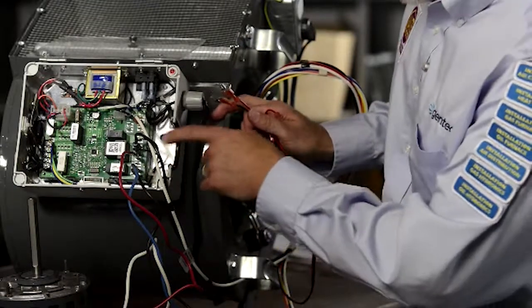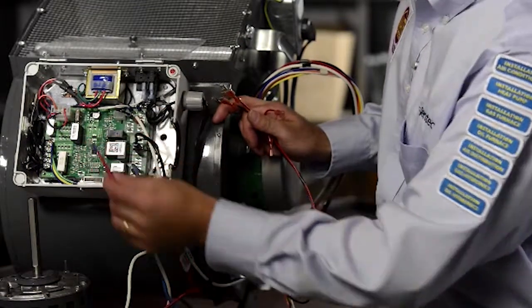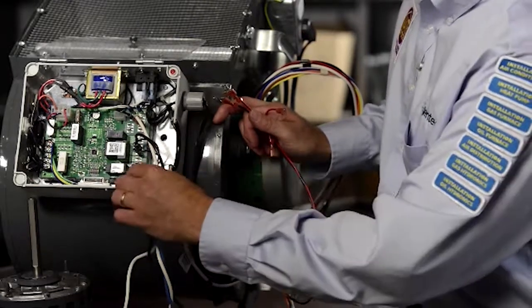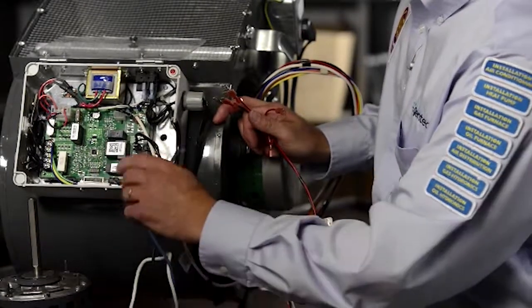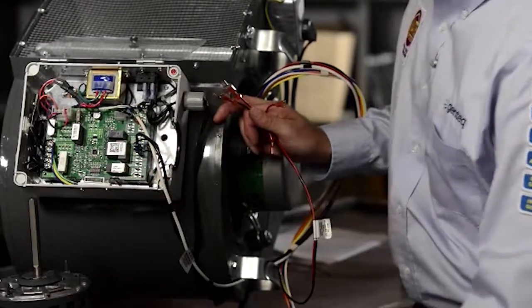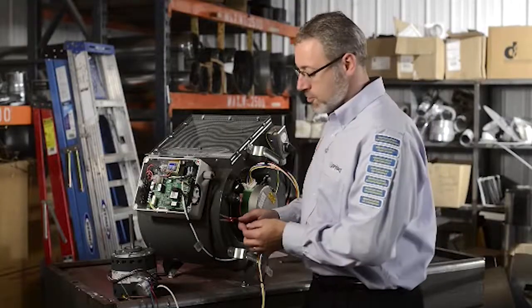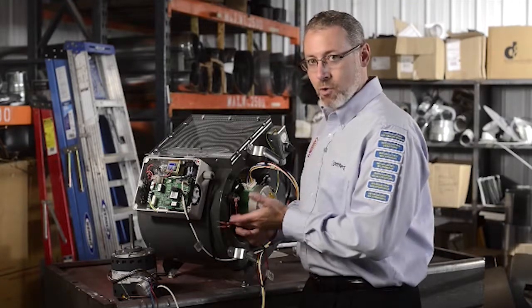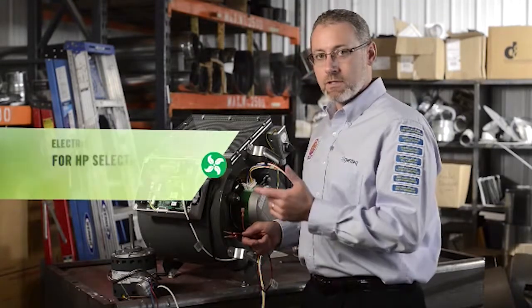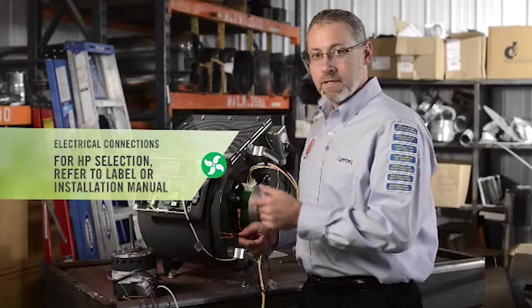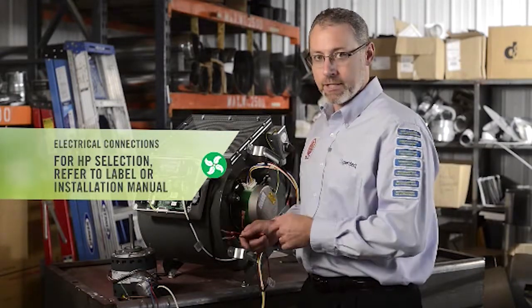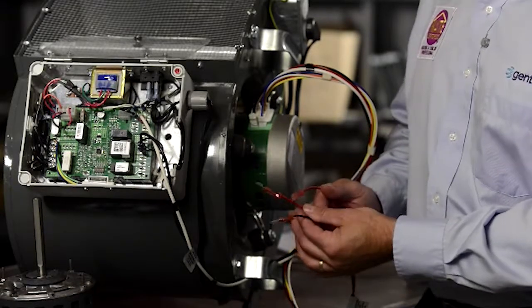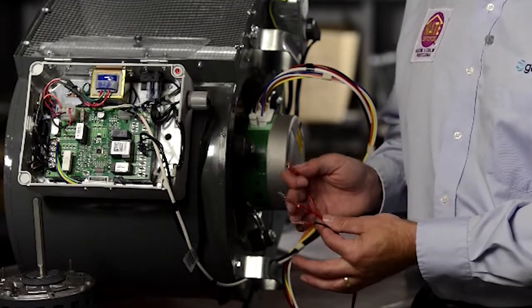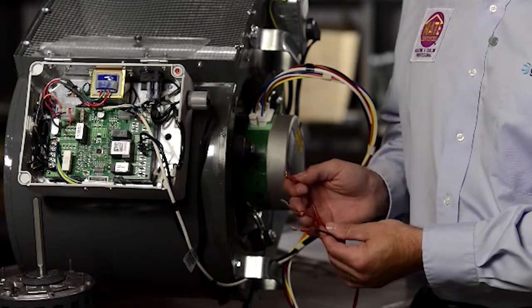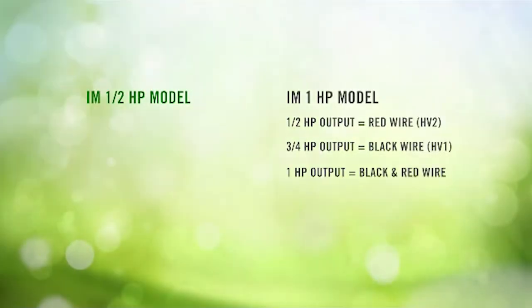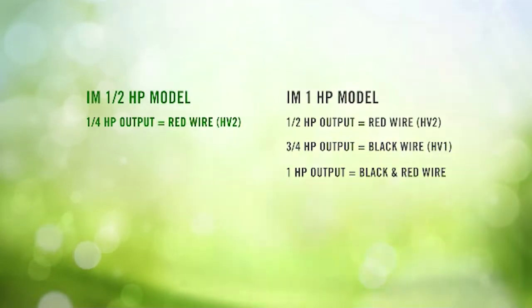So the first thing we're going to do is go to the HVAC control board, find our speeds from our PSC motor, and disconnect them from the heat taps, the cool taps, and the continuous fan tap, if applicable. Next, we need to determine, do we need both of these wires or just one of them? For that, we're going to go to the label on the motor or the installation manual for our horsepower selection guide. You see, these wires don't just tell the motor when to turn on, they also select the horsepower from its multi-horsepower capability.